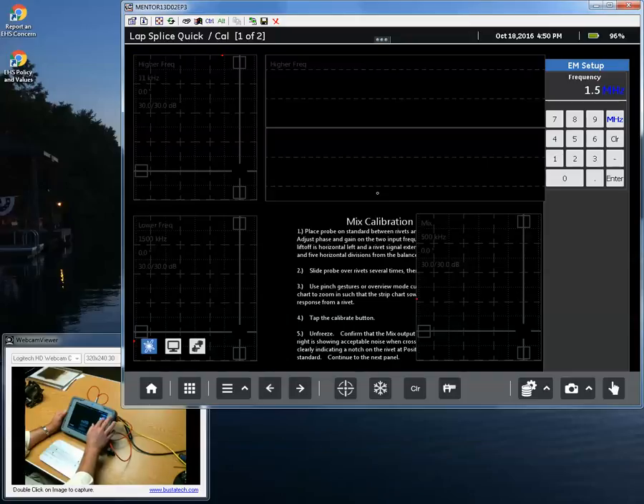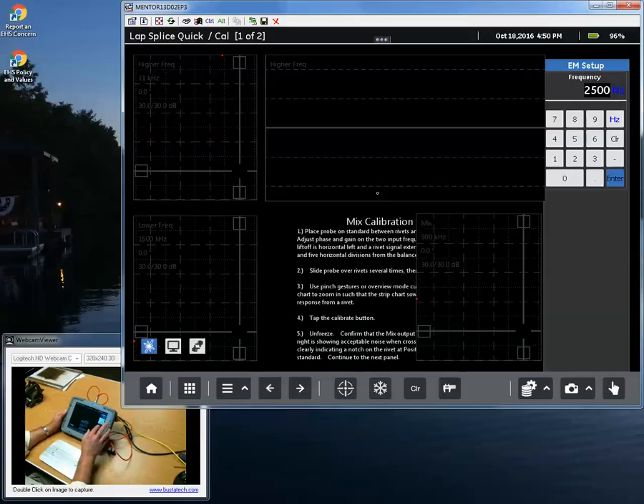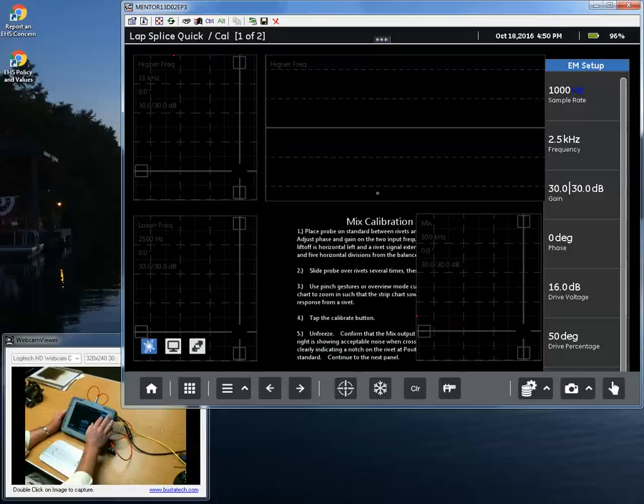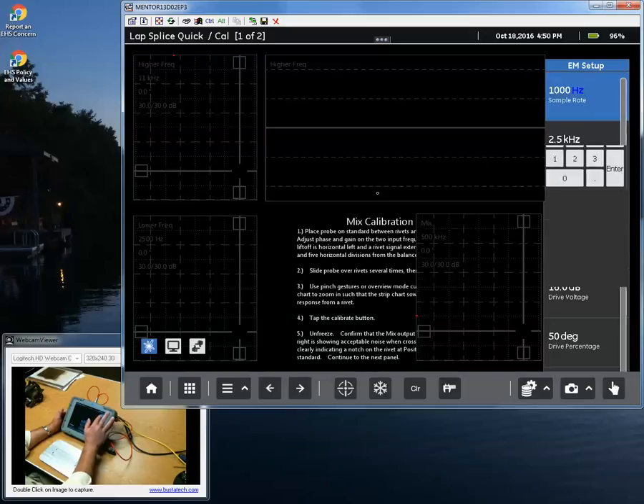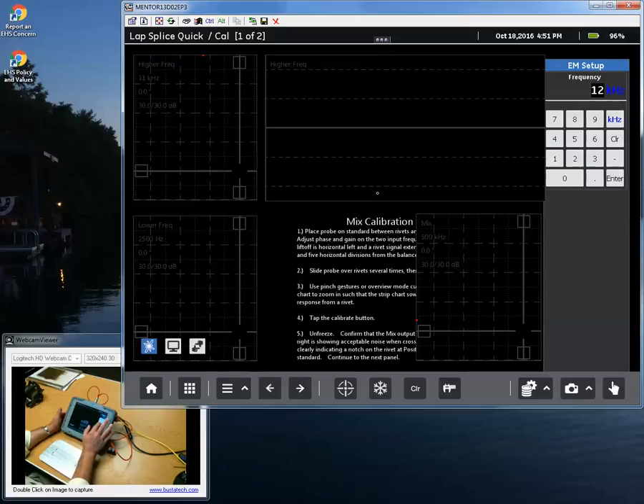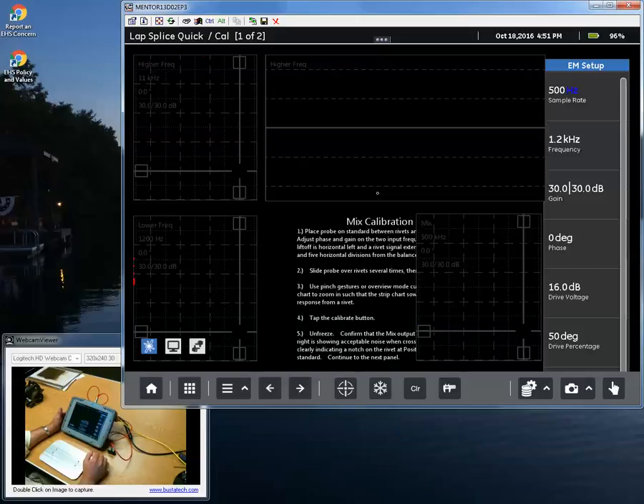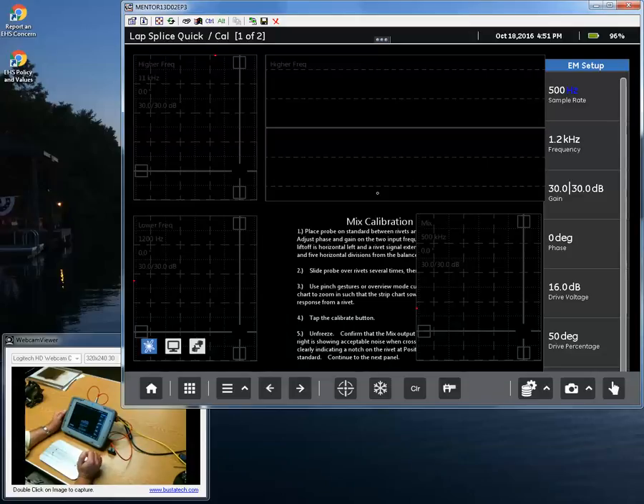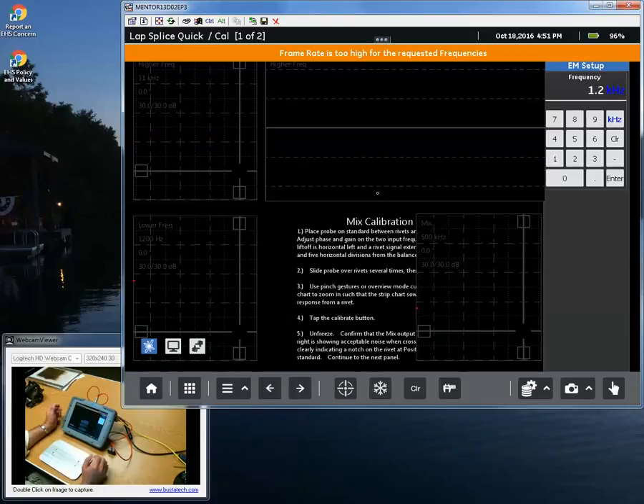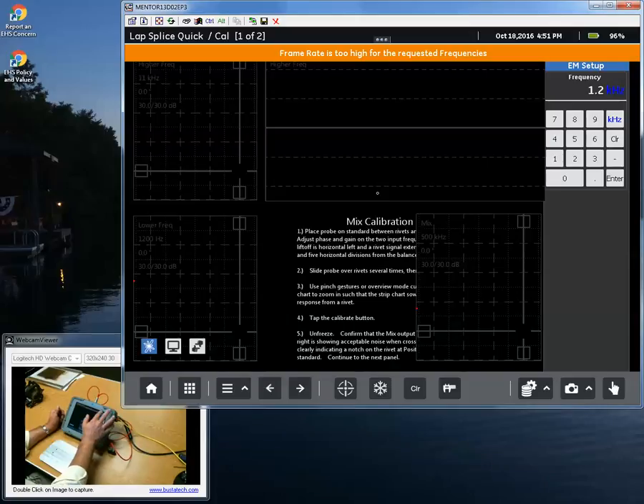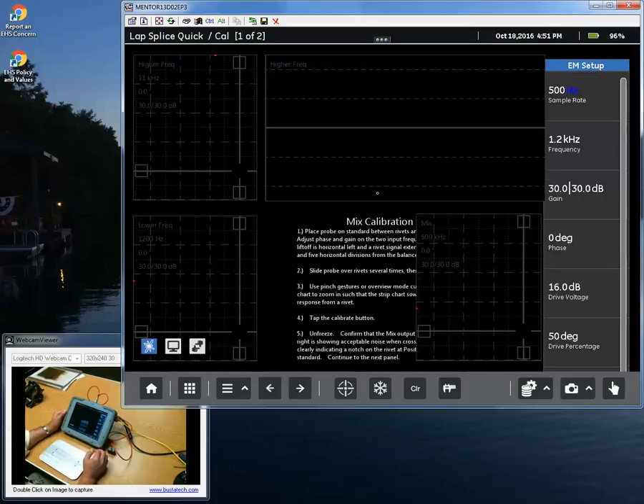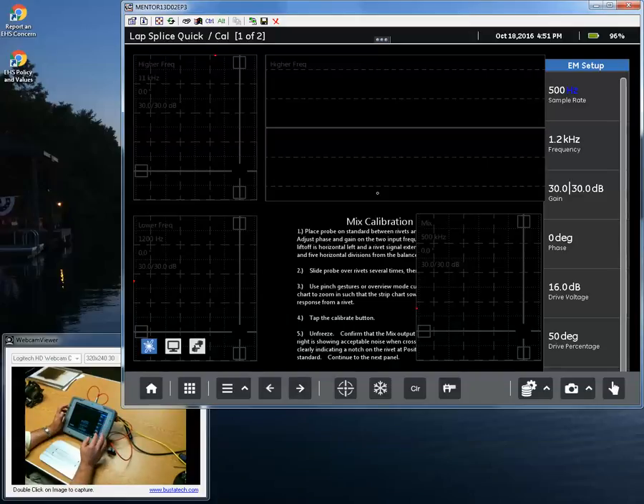If we go to 2,500 hertz, 2.5 kilohertz, that's okay because it's more than twice our sample rate. If we wanted to go to a 1,200 hertz frequency, we would have to first take our sample rate, lower it to 500, then we can take our frequency down to 1.2 kilohertz. As long as we keep our sample rate less than half of the frequency, the instrument's happy. If we try to break that rule, go to 800 hertz, it doesn't like that. It's important to keep the sample rate at less than half.